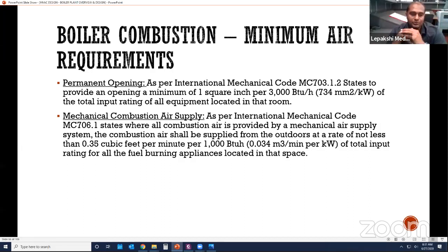Before we come up with the loads, how are you going to calculate all that? Once you calculate everything, you size the equipment that's needed, and then you have to come up with the louver dimensions. The louver dimensions are based on this. That's how you come up with the size of the louver. Sizing the louver is the most important thing when it comes to combustion air.